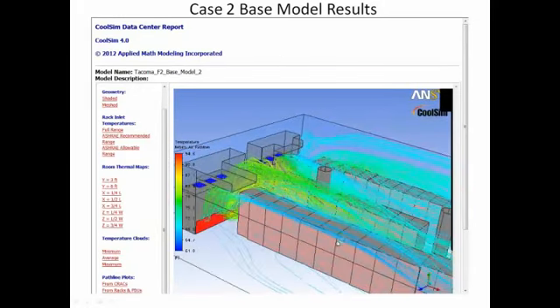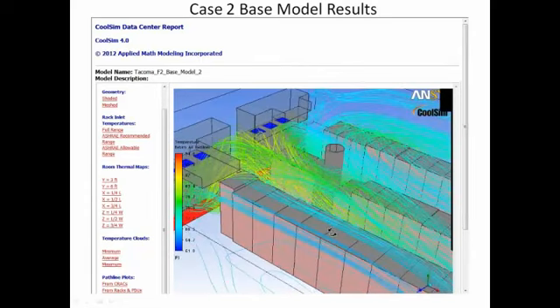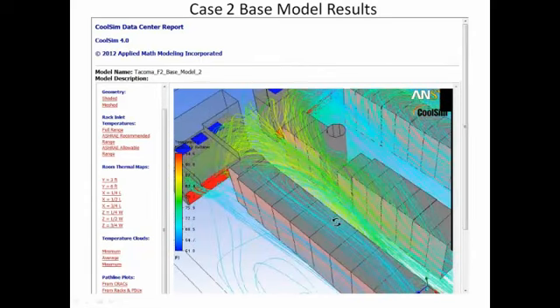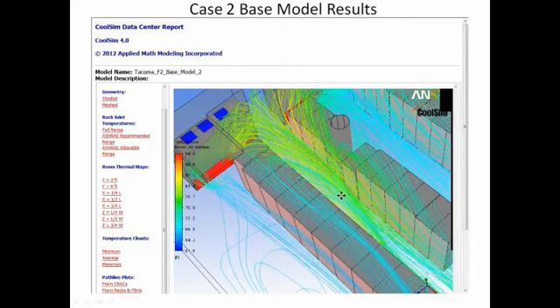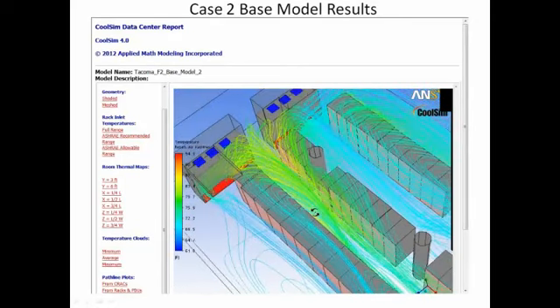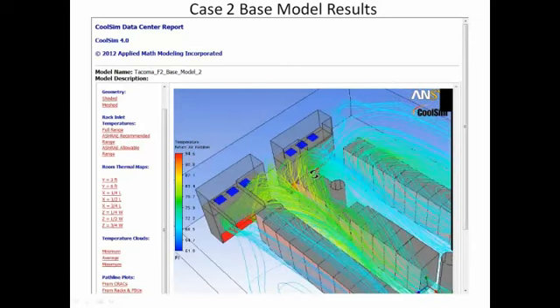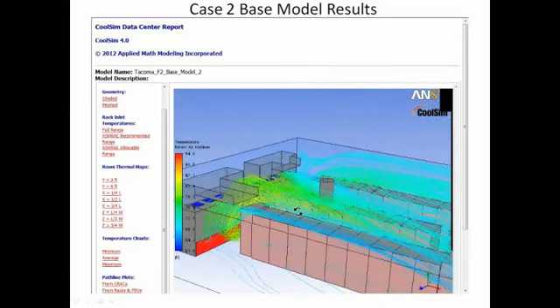And you see here what's happening is the hot air is coming out of the hot side of these units, and they are arranged in fairly good order. I've got a cold aisle here down the center. I've got a hot aisle here. They're all facing correct. But look where the cooling returns are on this one, Magnus. They're down at the bottom.